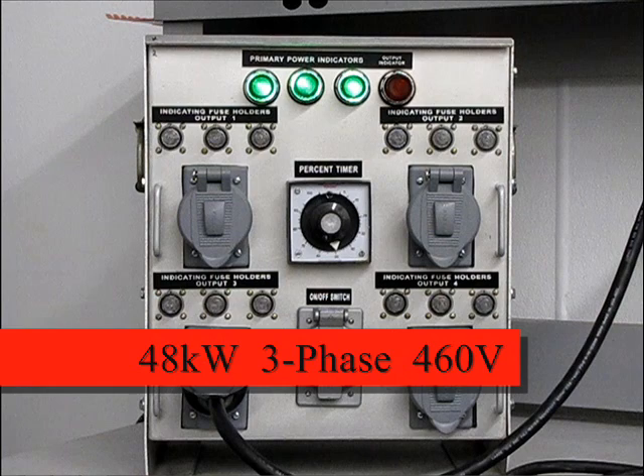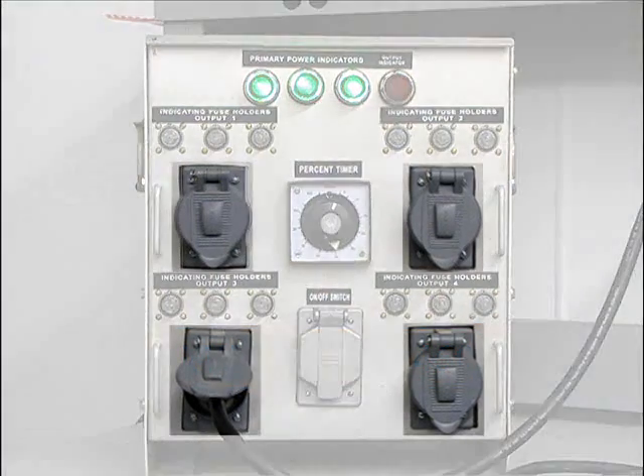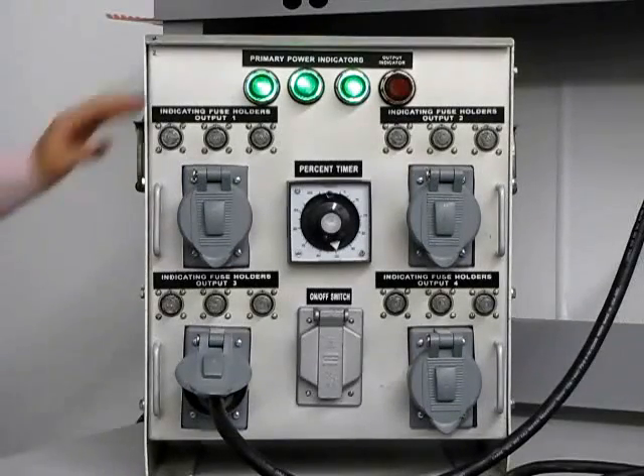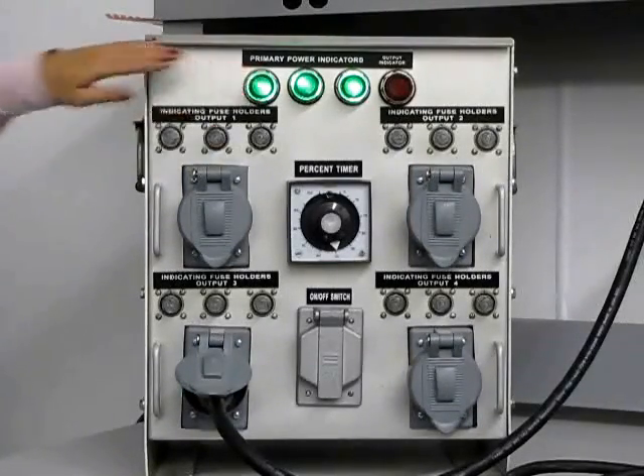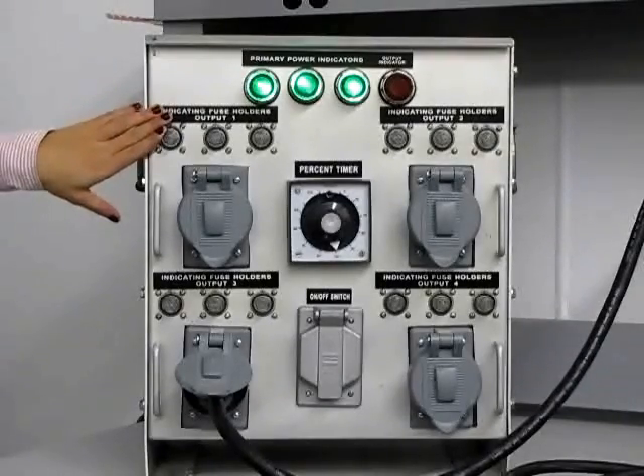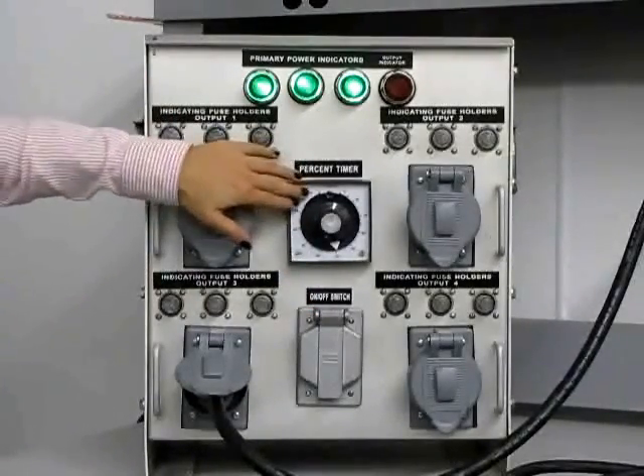The controller is designed for three-phase, three-pole, four-wire primary input and has four three-pole, four-wire receptacles for secondary output. It comes with power available indicators, blown fuse indicators, a disconnect switch, and a percentage timer.